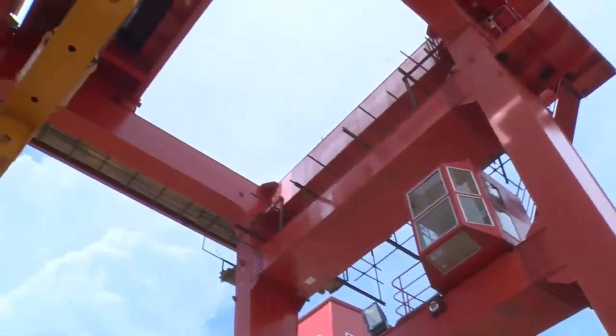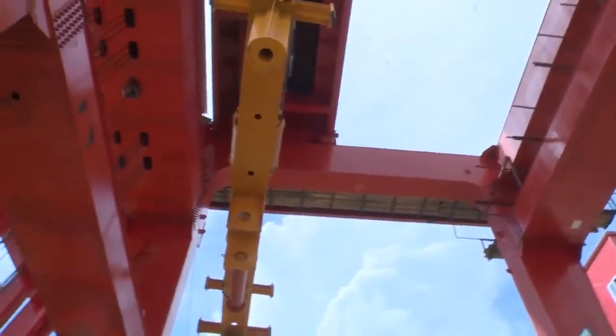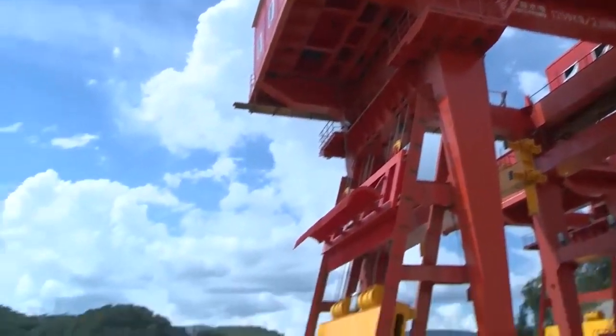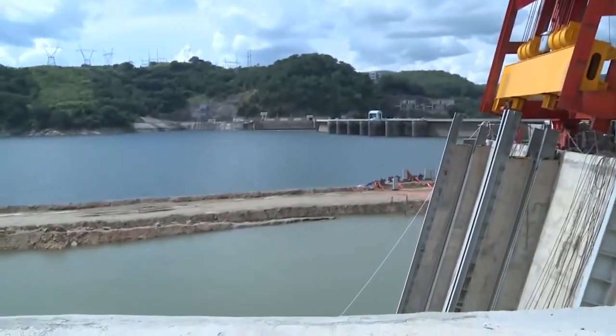Before power generation can begin, the intakes must be inspected for leaks. For each unit, Unit 7 and Unit 8, we have 2 gates, the emergency gate and the service gate. At the moment, we started by installing the gates. Once they have been installed, we fill the intake area with water so that we can perform leak tests.